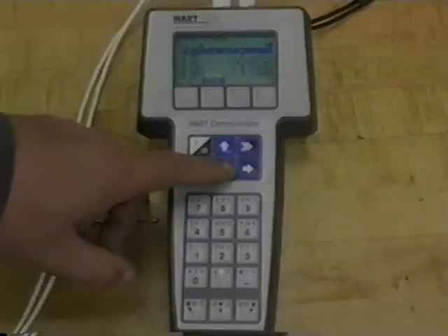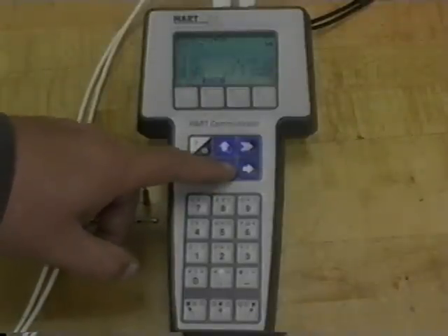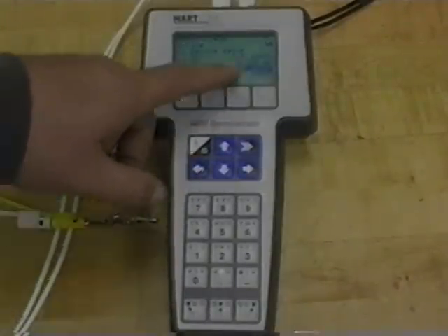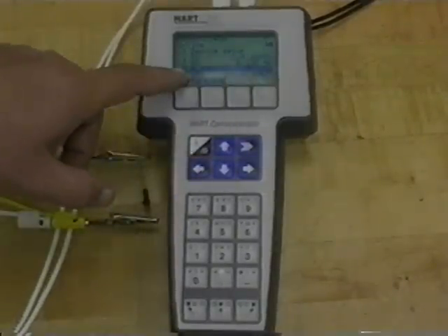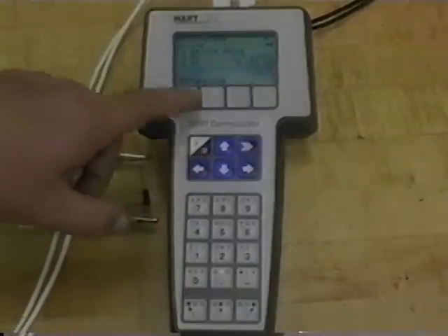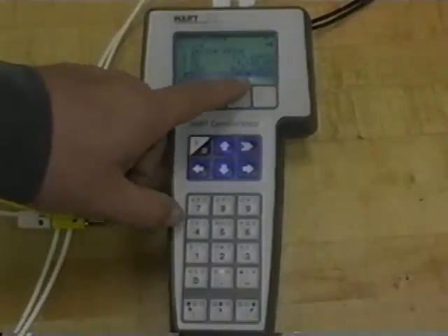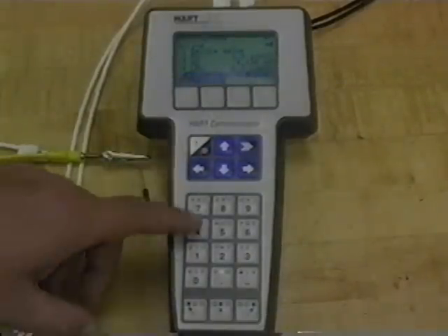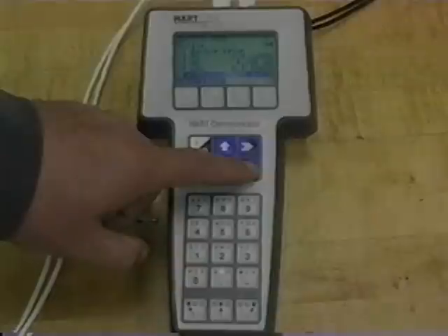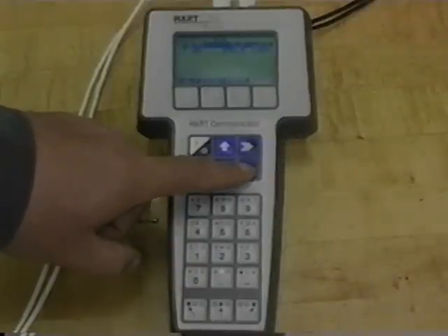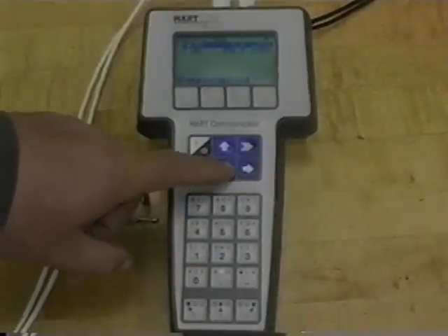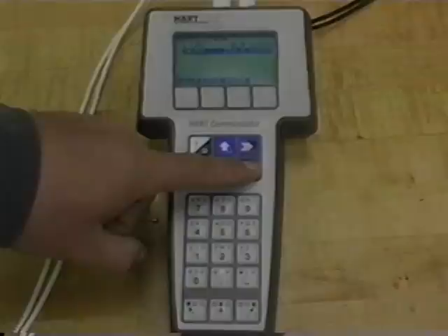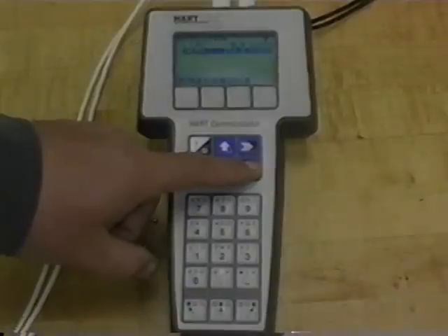If I back out of there and come back to the main screen, I can now change the calibrated range. It's set up for 0 inches of water at its low range value to 250 inches of water for its upper range value. All I need to do is move over to the right, go down to upper range value, move over to the right again.